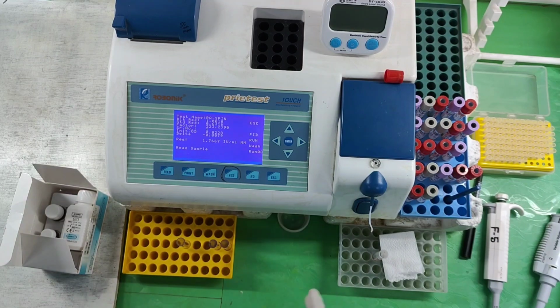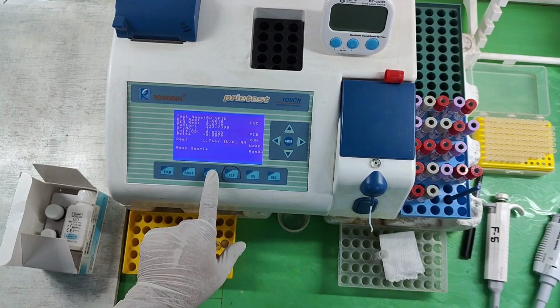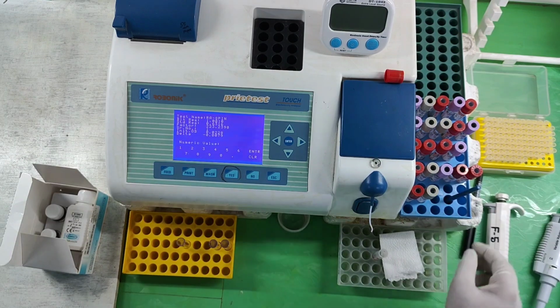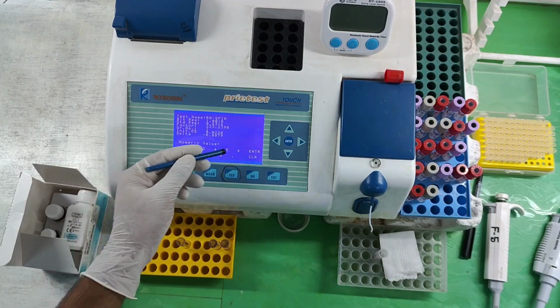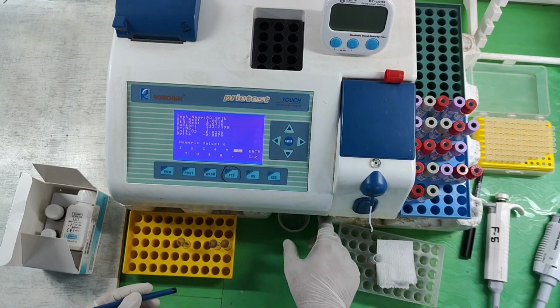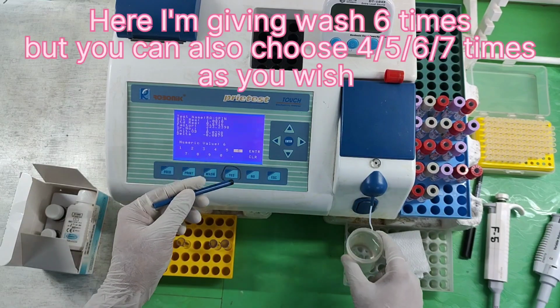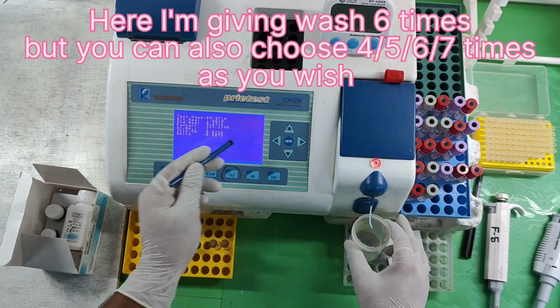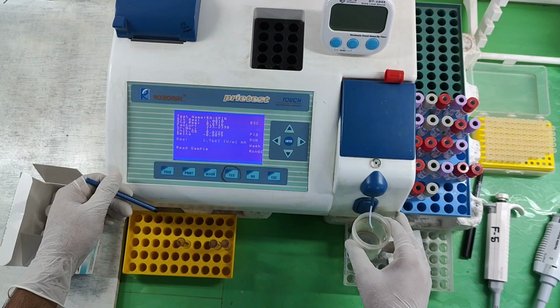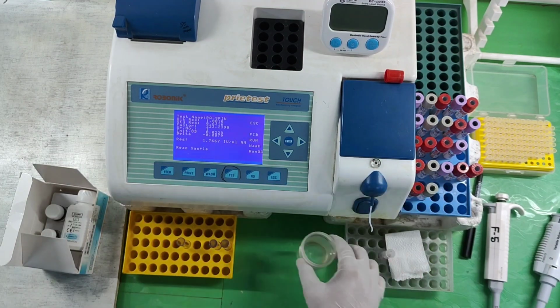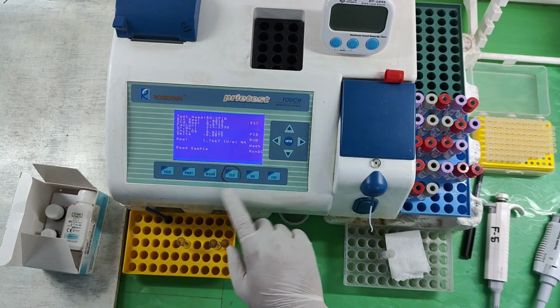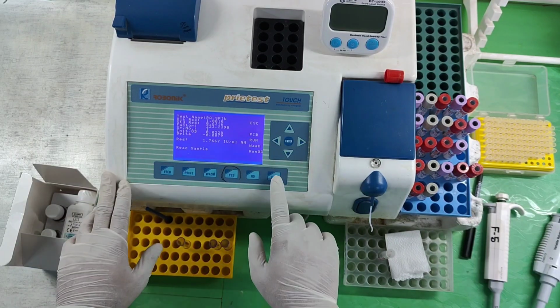Now, after running any test, you have to wash this machine. That's why here is a wash button. I have to select wash, and next, how many times? 6 times. 6 times wash with distilled water. Place the distilled water here and enter. The machine blinks and distilled water is getting down. After this, we have to escape.